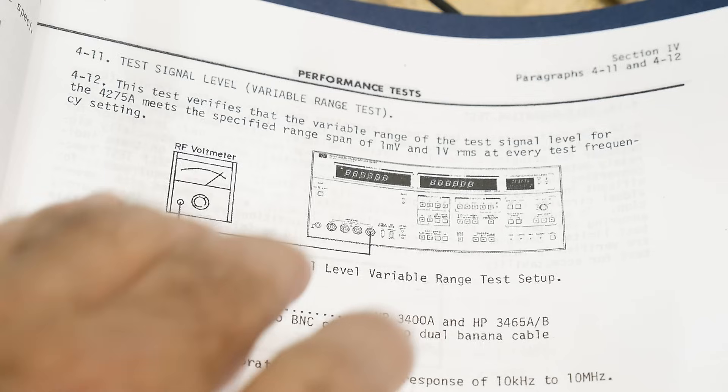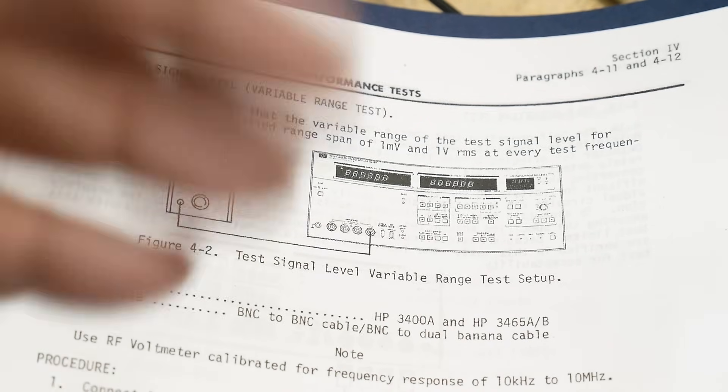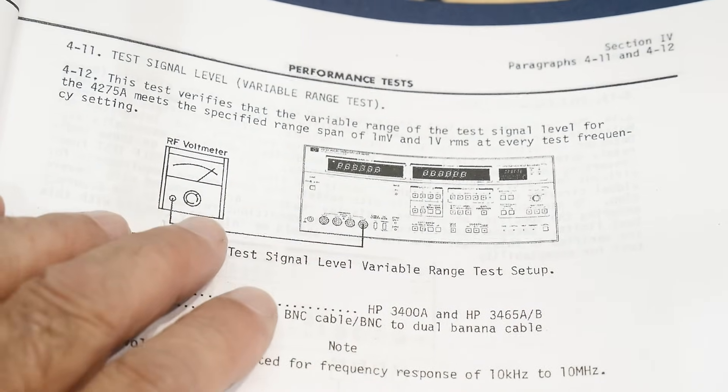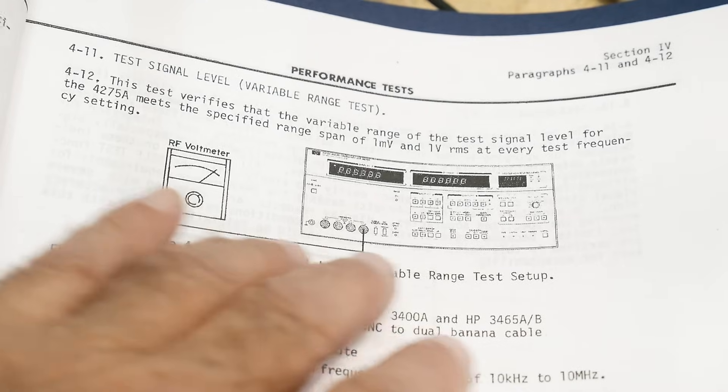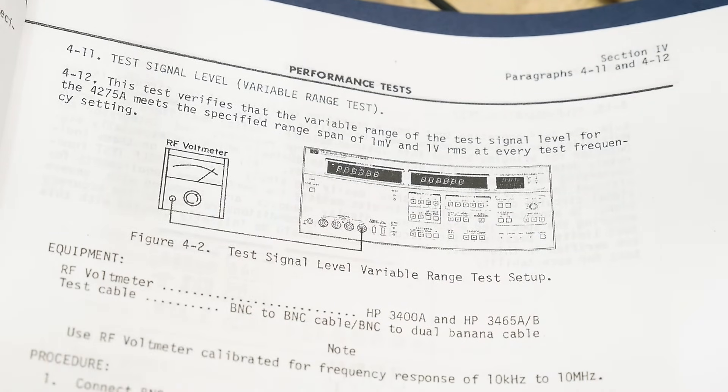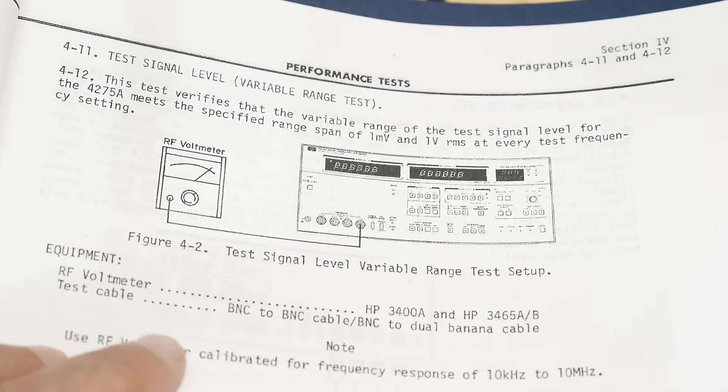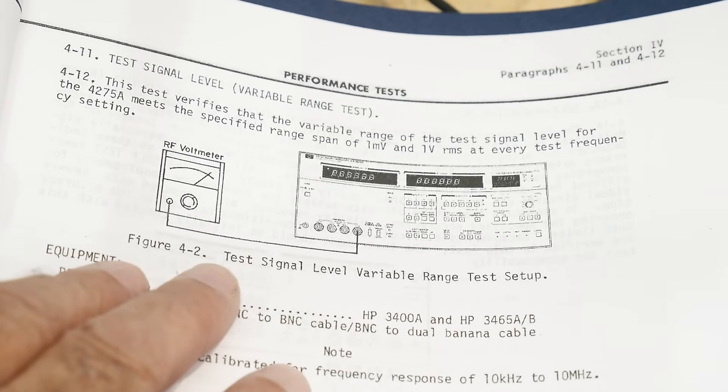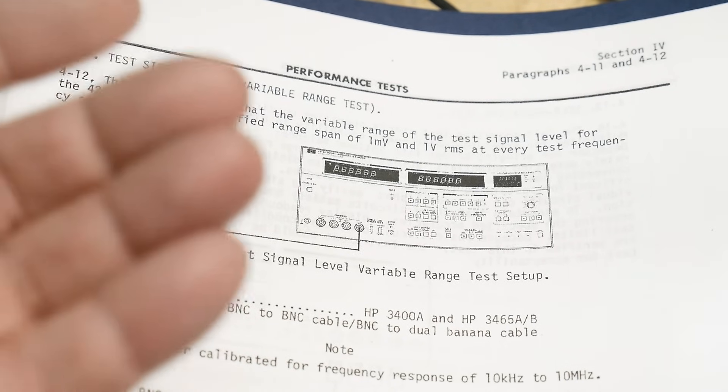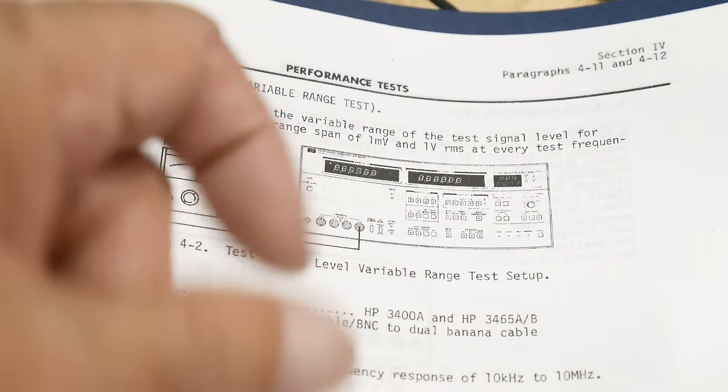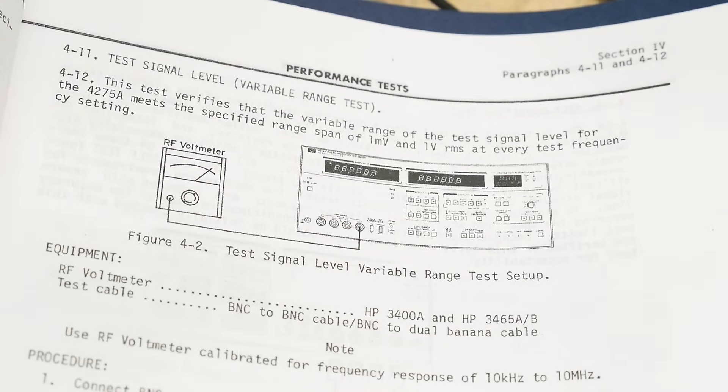The next test is, is it outputting the voltage that you want? It has three different ranges, and it has a knob that you can turn to set the output voltage of the signal. This is a vector voltmeter, so you want to output a known frequency and output a known voltage, and then it can do its math.